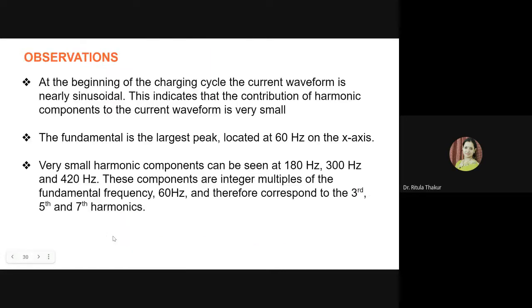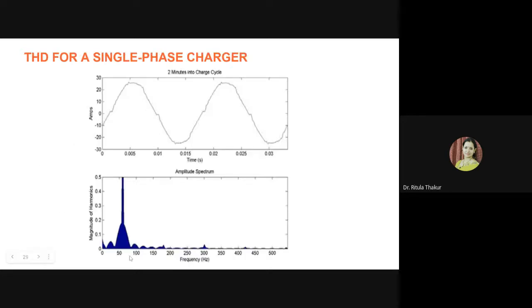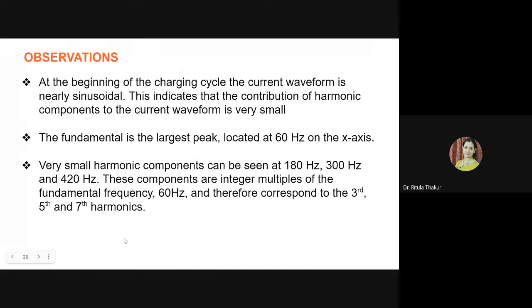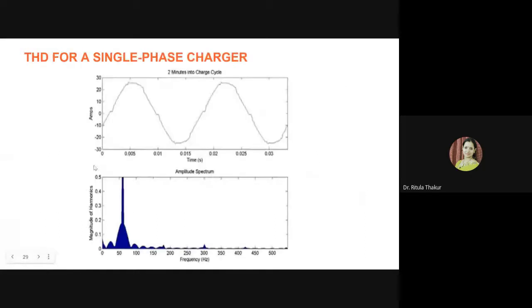So the observation is that at the beginning of the charging cycle, the current waveform is nearly sinusoidal. So the initial contribution of harmonic components to the current waveform is very small. As I said, the largest peak is the fundamental, approximately 60 hertz, and very small harmonic components can be seen at 180, 300, and 420. As you can see from here, 180 is the third harmonic, then the fifth harmonic is 300, and very small at 420, the seventh harmonic.